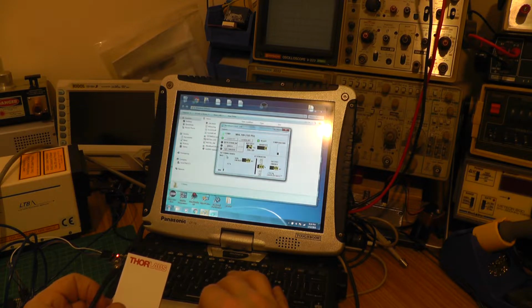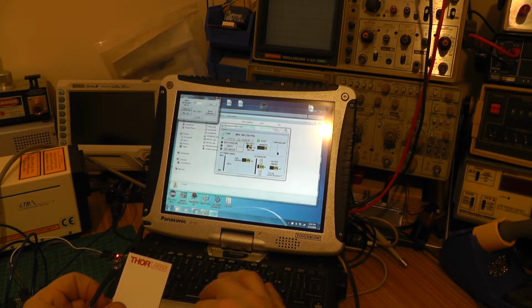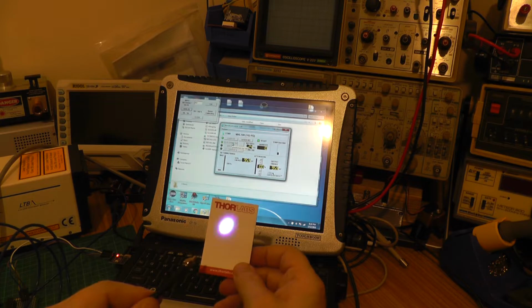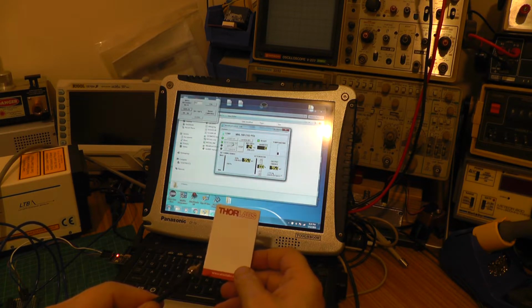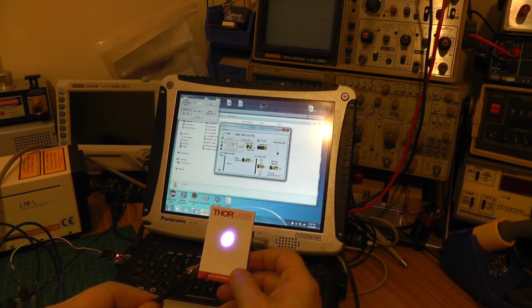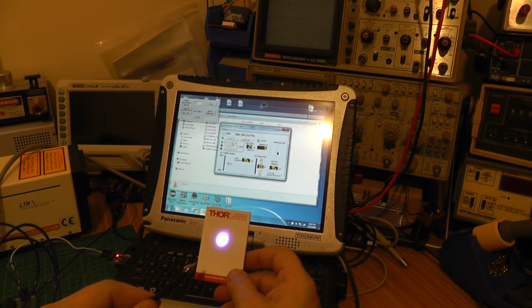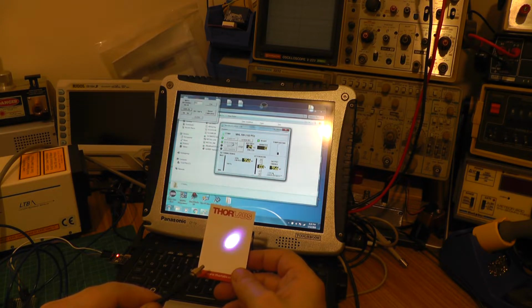So yeah, depending on the model of nitrogen laser that you get, you can actually tune the high voltage from minimum to maximum. Currently this is set to 15%. It looks like we can't actually alter it, but if you go into the calibration section, we can actually set the high voltage to 100% and then power it on. So there's our output, and according to the inbuilt energy meter, we're doing 95 point odd microjoules, which is not bad. I mean, the laser's done like 6 million shots or so, possibly more. I don't know how big the buffer is in these things, but yeah, pretty cool. So we ought to be able to drive a dye laser at some decent repetition rate with this.